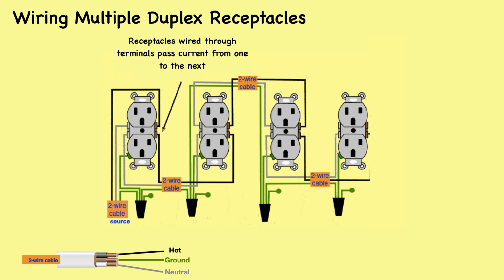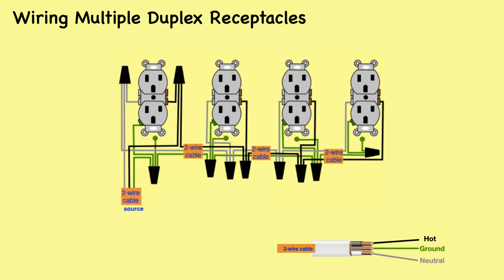In conclusion, while wiring outlets together using the device terminals can be a convenient and efficient method, it is essential to be mindful of the potential weakest link problem. By following proper installation procedures and practices, we can ensure the safety and reliability of the electrical system in residential spaces. This diagram shows the wiring of the same multiple receptacles in an arrangement that connects each individually and to the source using a pigtail splice.